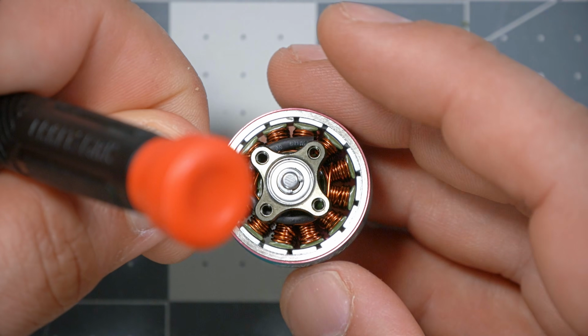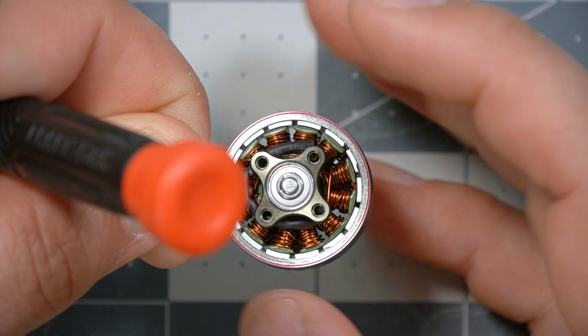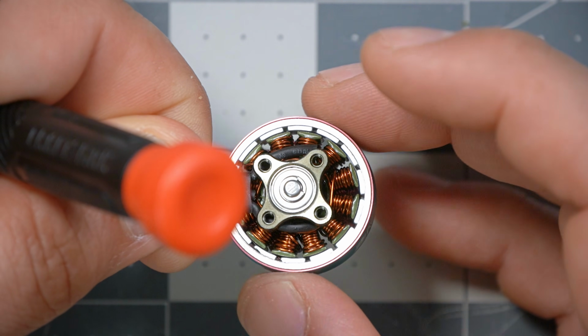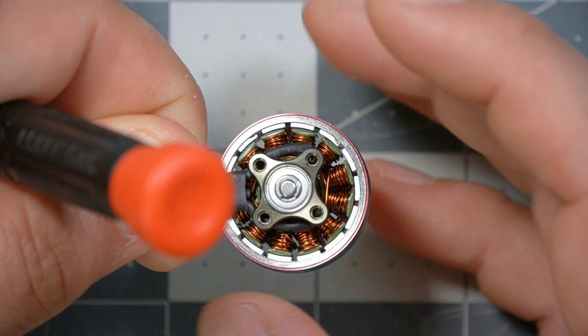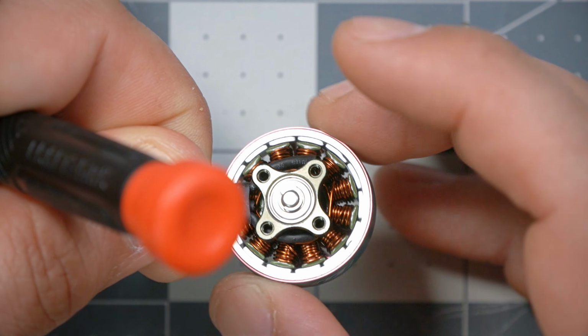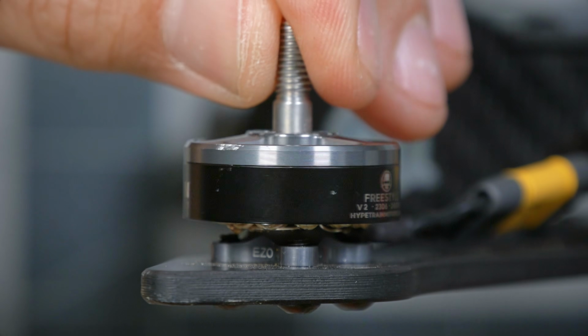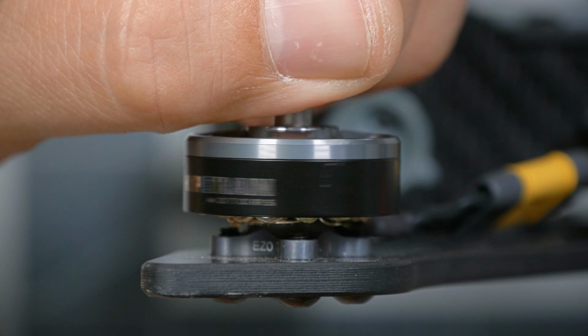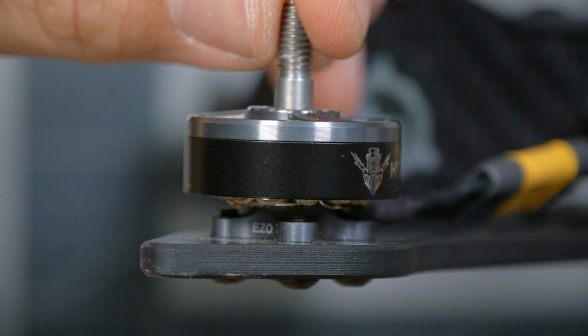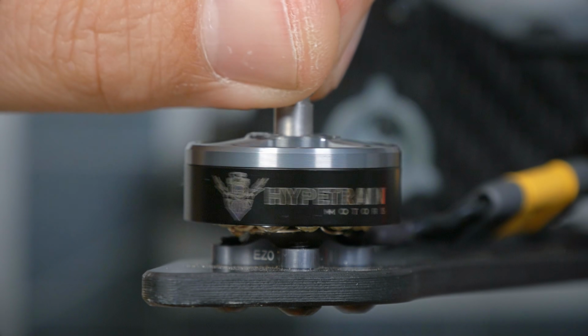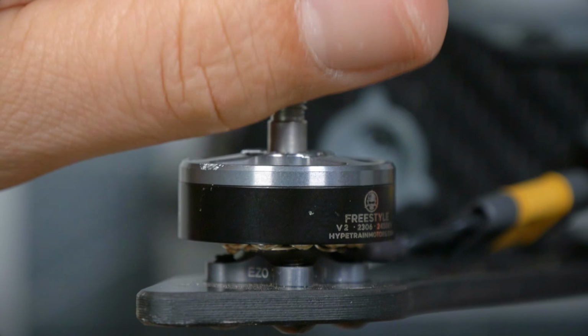If the shaft is bent, or if the bell is out of round, if it's an oval instead of a circle, what we'll see and feel is that as we rotate the bell, there will be a rubbing at certain points. It's usually not all the way around. It's usually like right here you'll feel a rub and then it'll release. That's another thing we're going to check for when doing our physical inspection of the motor. But with this motor, I don't feel any rubbing at all. It's perfectly smooth all the way around. It's just that there is a sort of constant drag.